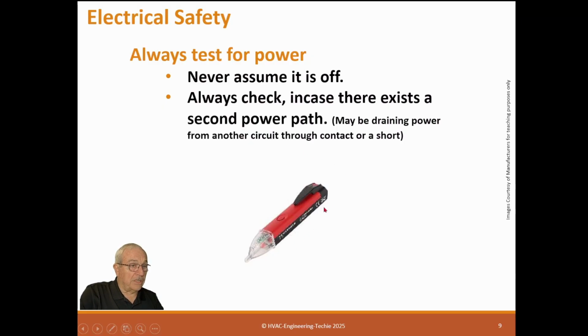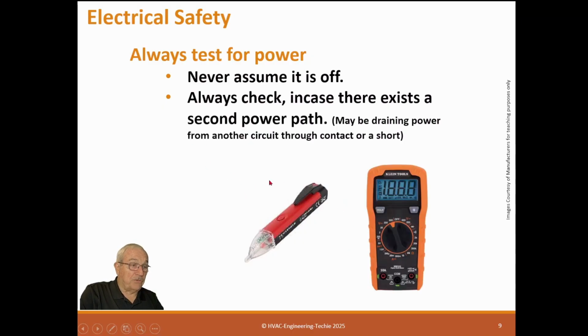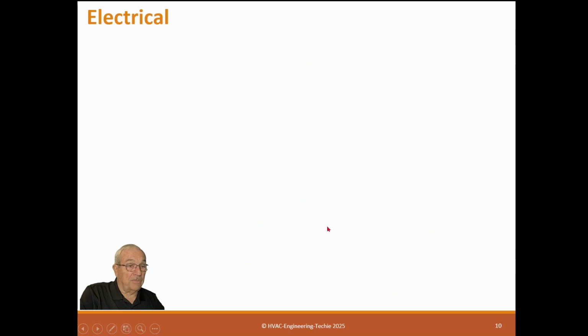And then we use tools. This is a ticker, where basically you get it close to power and it starts lighting up. It tells you there's actually live power. But I wouldn't rely on this solely. If I'm an electrician in the field, I want to take a meter and put it on there to test that there's absolutely no power. Now, just so you know, sometimes when you plug a meter in there, it'll show you've got millivolts on the circuit, or you might even have 1 or 2 volts. That's somewhat common to bleed by in our modern day world. It uses a lot of triacs and a lot of transistors. They can actually leak to the ground side or leak to the common side. So there can be a few little trickles of voltage. That's not uncommon. Doesn't mean the circuit's active. It just means that somewhere there's a diode feeding back.